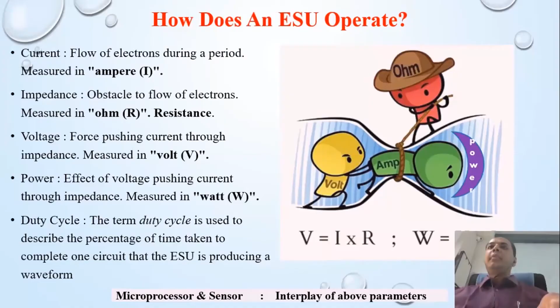Duty cycle is the generation of alternating current for a percentage of the time it takes to complete one circuit. If an ESU generates current for 80% of the time and keeps it off 20% of the time, it is known as an 80% duty cycle. Tissue effect varies with waveforms. In the figure, if you compare 50% duty cycle with 6% duty cycle, you can see that the peak voltage rises. This is because the ESU is trying to maintain constant power, which is set by the surgeon, because of the off time of current, due to variability in the duty cycle.